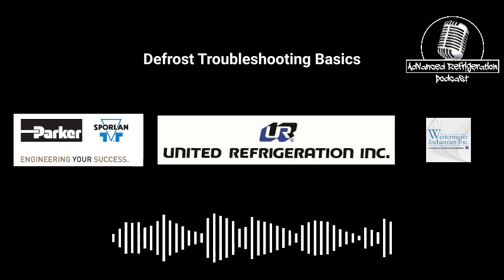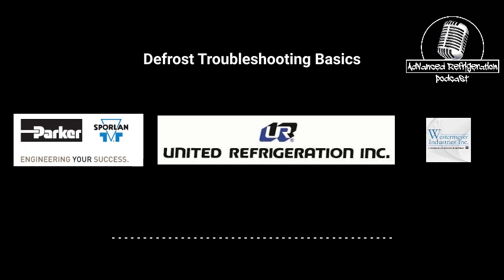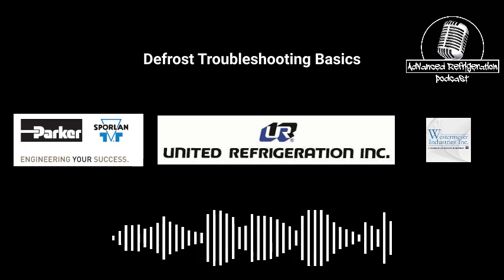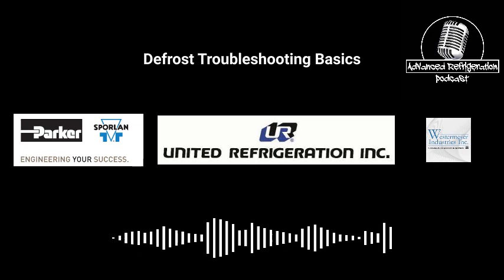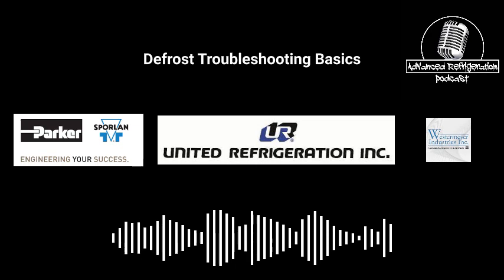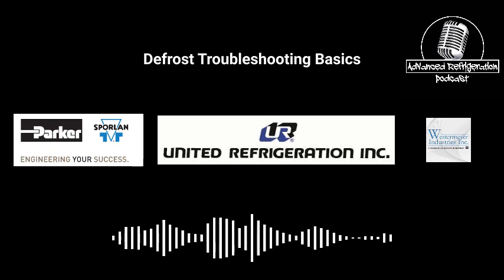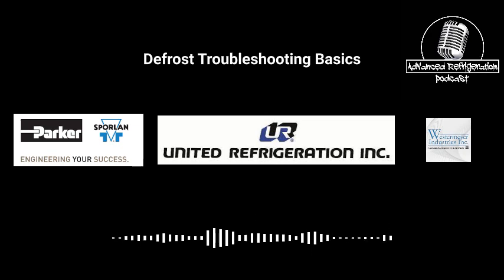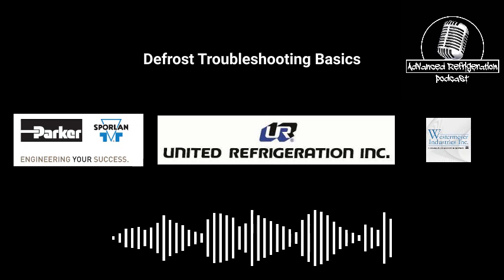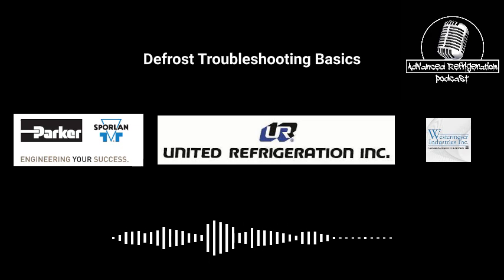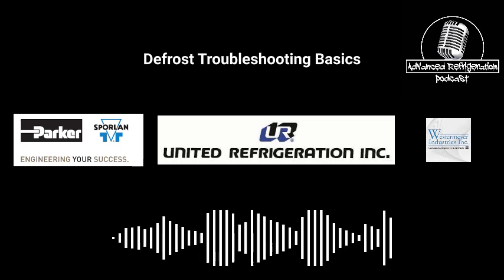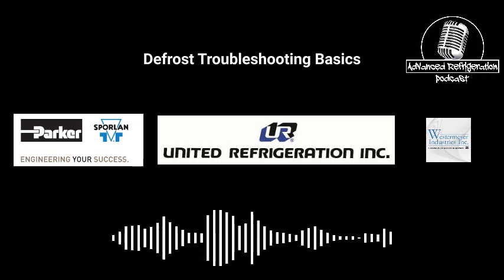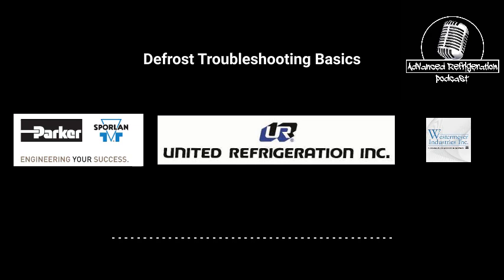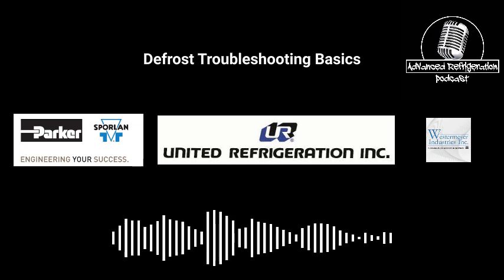Now, the other thing behind that is it also helps the post defrost spikes. So you don't want to slam a 2 5/8 suction line full of warm vapor back on and just bang on like 5 or 6 compressors, and then the rack overshoots and undershoots and overshoots, and then you get this almost pulling a vacuum thing. So if you could pump that thing out, you avoid all of that. You just get a smooth startup. It just clicks on, ready to go, and next thing you know, the coil's open, it's down to suction pressure, it's ready to roll.